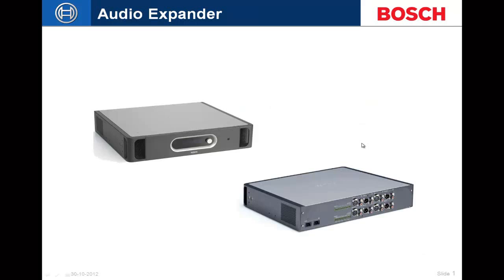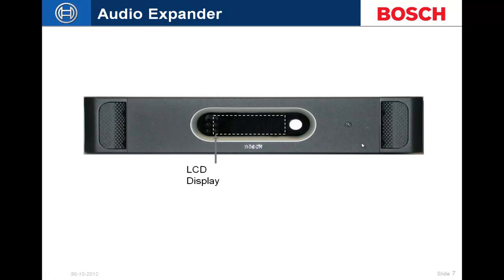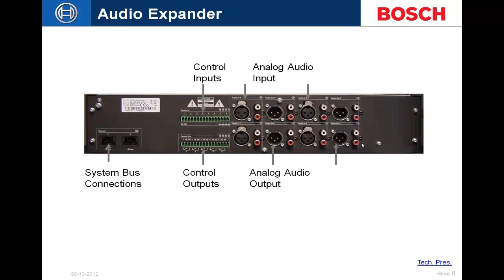The audio expander is an expansion unit with the same audio inputs and outputs as the network controller. However, it does not have TCP/IP input or a front-mounted speaker. It provides control inputs, control outputs, and analog inputs and outputs — four in and four out in both RCA and XLR. Control inputs are supervised, same as the network controller. All five control outputs are accessible. It is not a power supply; it is powered via the system bus from the network controller.